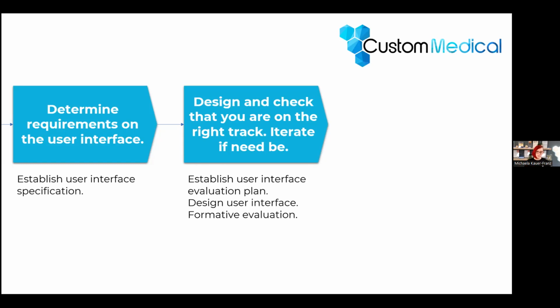Just one word of caution. As I told you in the beginning, I've been doing usability testing for almost 20 years now. And to be honest, I have never ever seen a user test of a product run smoothly for the first time. So if you haven't tested your product during development with users, I am almost 100% sure that your summative evaluation will not work the way you expect it to. So therefore, if you have the time and you're developing something new, invest some time into formative testing just to make sure that everything's on the right track.